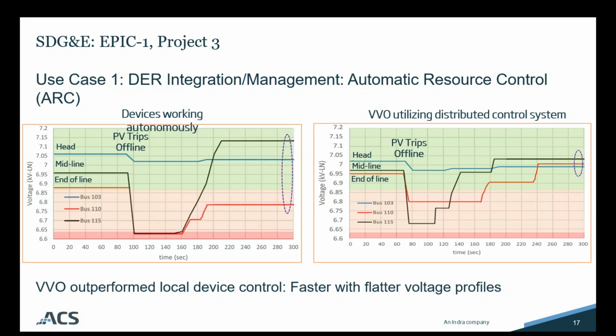So some things that we can take from this. First, the chart on the left shows the devices working autonomously. These are just the voltage and capacitor control devices working autonomously based on the conditions that they're seeing on their part of the feeder. So some takeaways we can take from this is, first of all, in the steady state condition, prior to anything happening, you can see that there's still a pretty large voltage gradient between both the head and end of line. It's not a very flat voltage profile. So again, as voltage becomes more dynamic, as more intermittent generation comes online, you have less flexibility along that feeder.